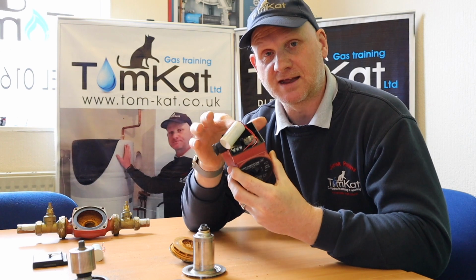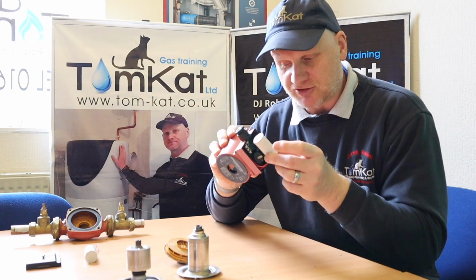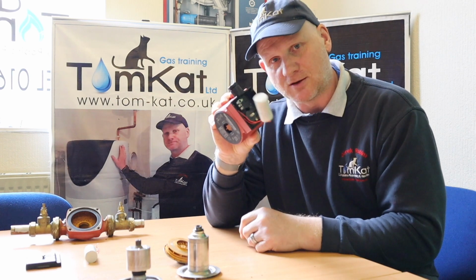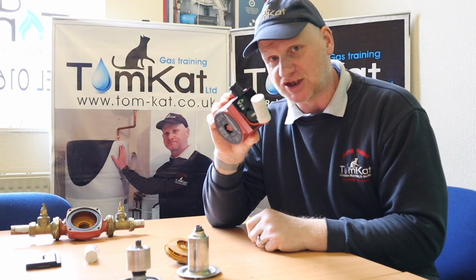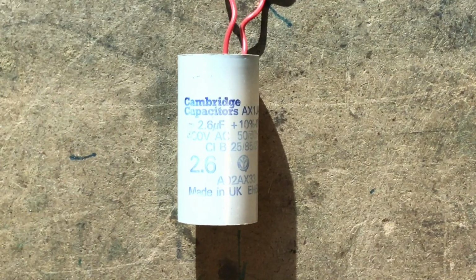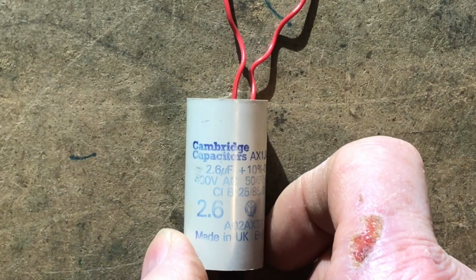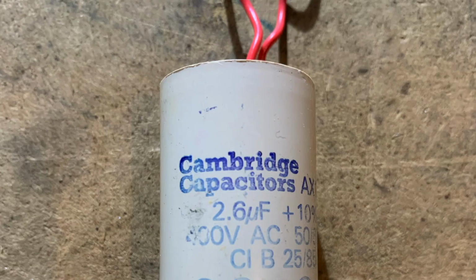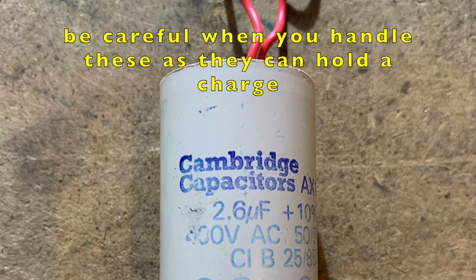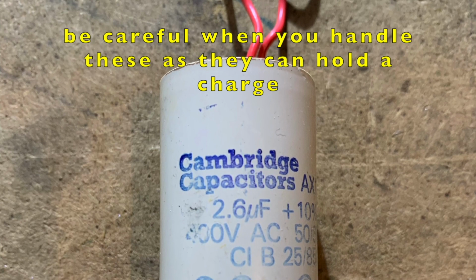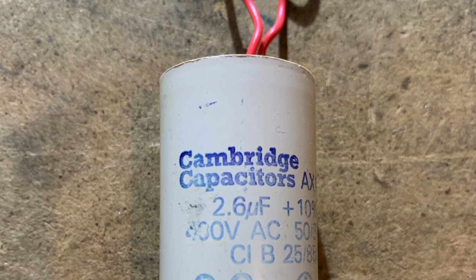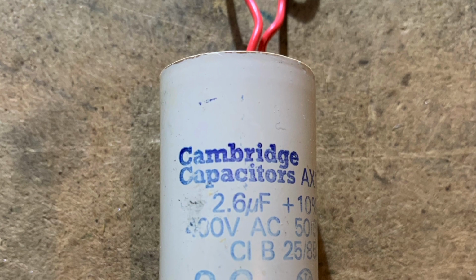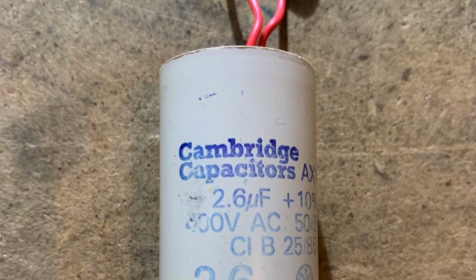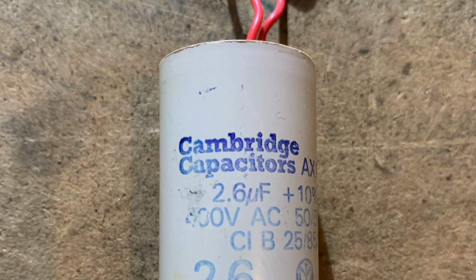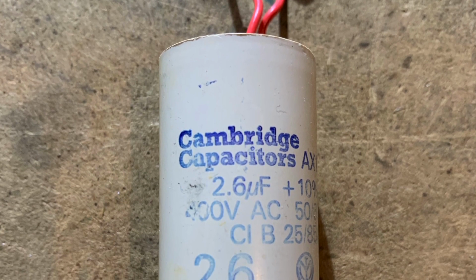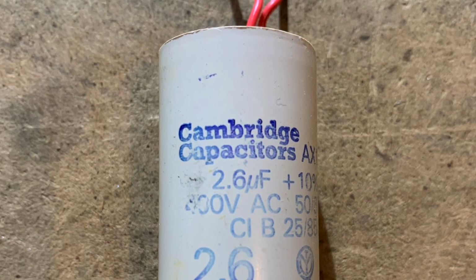Now let's have a look at the electrical side. The first thing we see on the electrical side is this thing hanging out. So let's find out what this is and what it actually does inside this pump. So you can see from the writing on this, it says it's a capacitor. So what's a capacitor? Well, basically it's like a battery because they store energy. But the difference between this capacitor and a battery is the capacitor can store and replace the energy a lot quicker than a battery can. But the battery does have one over on the capacitor, that it can store a lot more energy for a lot smaller size. So that's basically what a capacitor is. It's some way of storing energy.